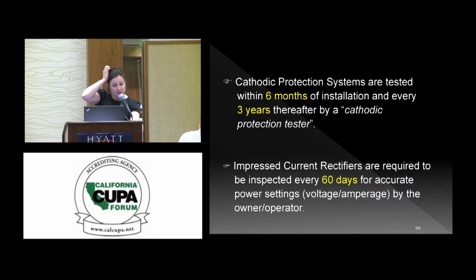Okay, just regarding testing, cathodic protection systems are tested within 6 months of installation and every 3 years by a cathodic protection tester, and that is actually defined in Chapter 6.7. It'll tell you exactly what a cathodic protection tester is.